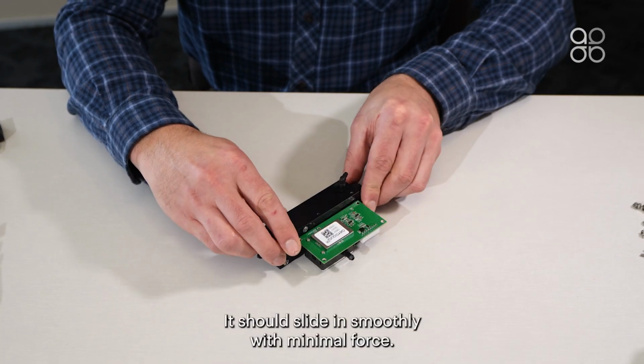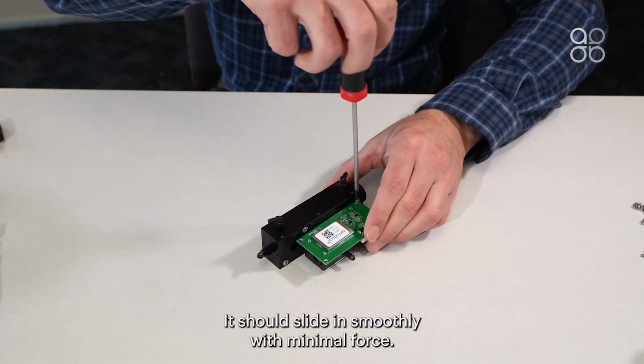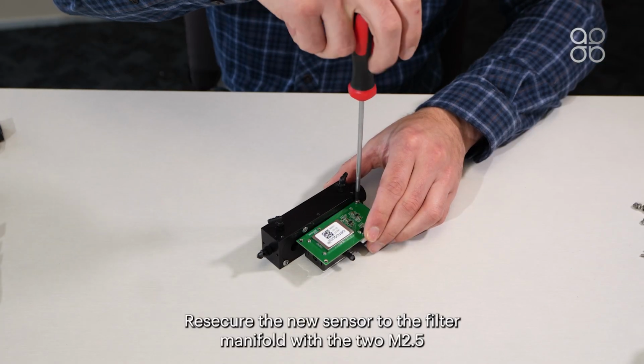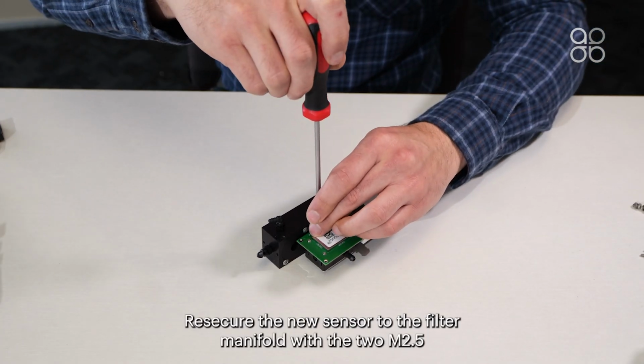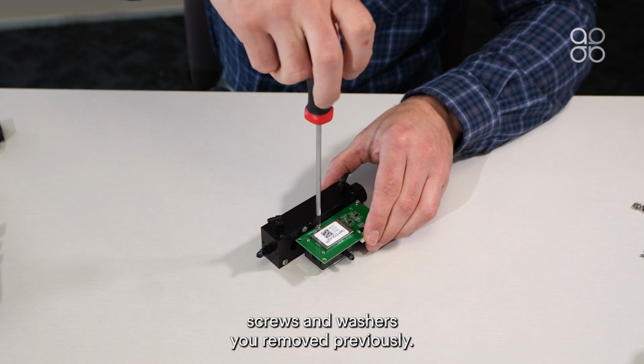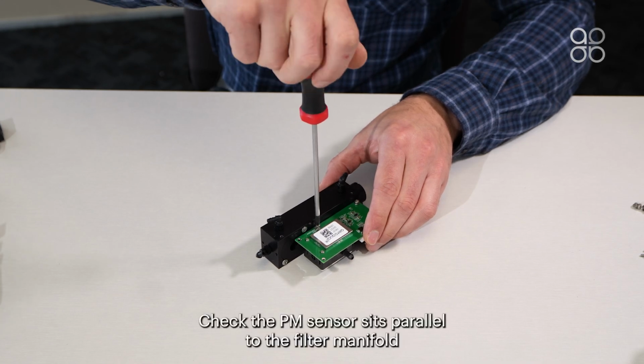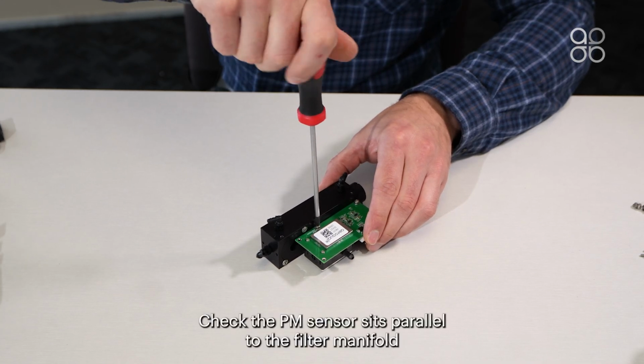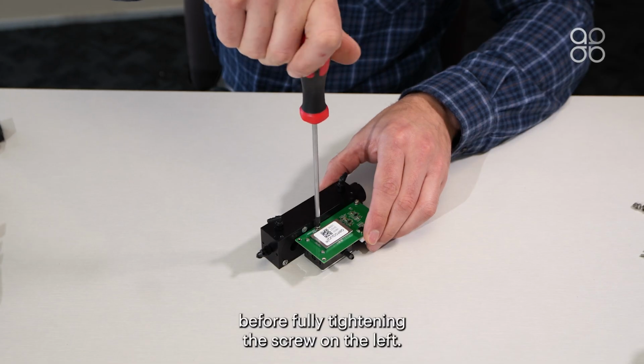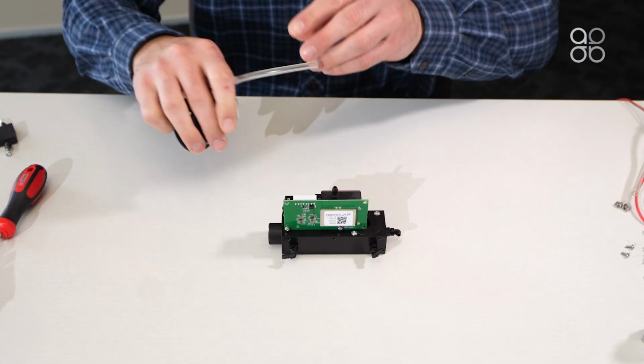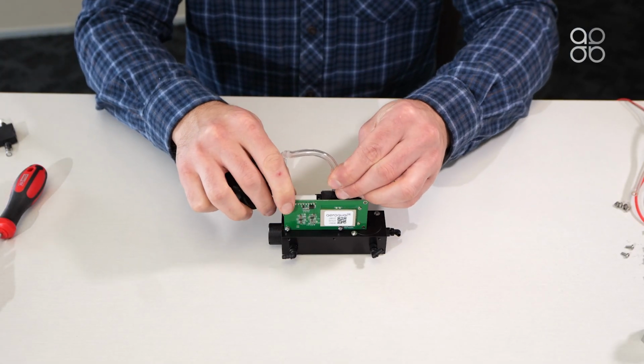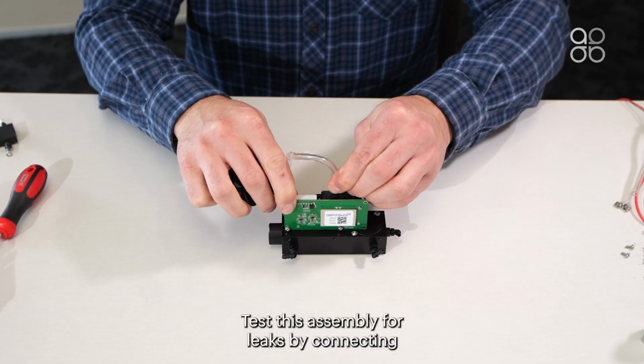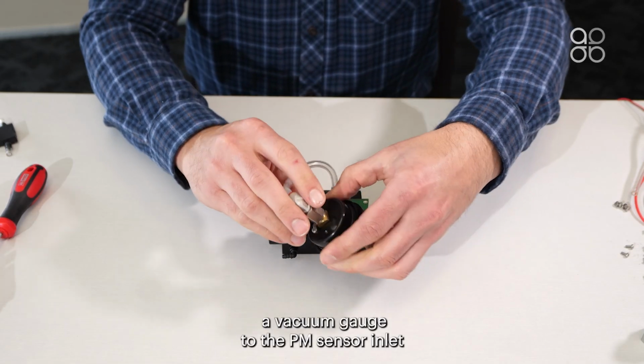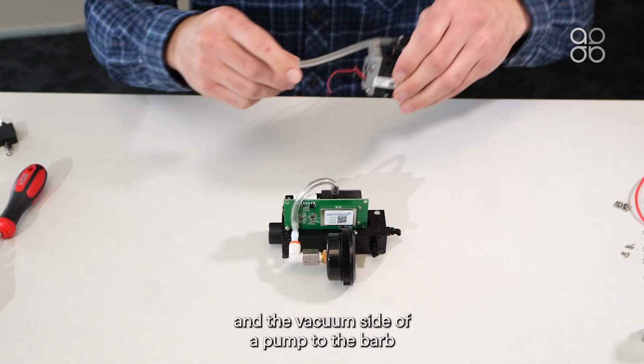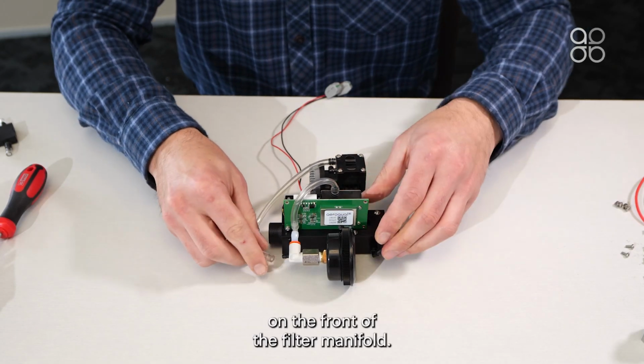It should slide in smoothly with minimal force. Resecure the new sensor to the filter manifold with the 2 M2.5 screws and washers you removed previously. Check the PM sensor sits parallel to the filter manifold before fully tightening the screw on the left. Test this assembly for leaks by connecting a vacuum gauge to the PM sensor inlet and the vacuum side of a pump to the barb on the front of the filter manifold.